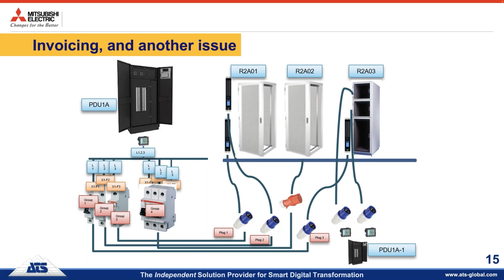So if a meter is not rightly configured, not rightly connected, not attached to a rack, or is the wrong type, it can have a very big error. Sometimes there's a small negative step in kilowatt hour values, which is a reachability issue. Sometimes there's a big positive or negative step in the month, which can be a replacement of a power meter or communication lost. Sometimes we see that just one current transformer is installed upside down.